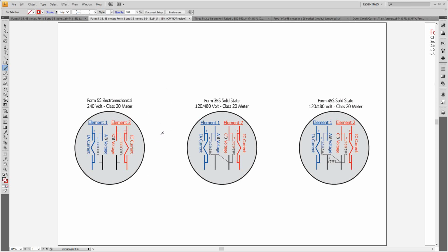In a solid-state meter, where you have auto-ranging potential coils, like the 35S that we used when I was in Utah working for Utah Power, we used an ABB meter that was a 35S. It was a solid-state auto-ranging Alpha meter. And in order to be auto-ranging, all the potential coils in the meter have to be tied to one common point. The 5S previously had two points where each potential coil was separate.